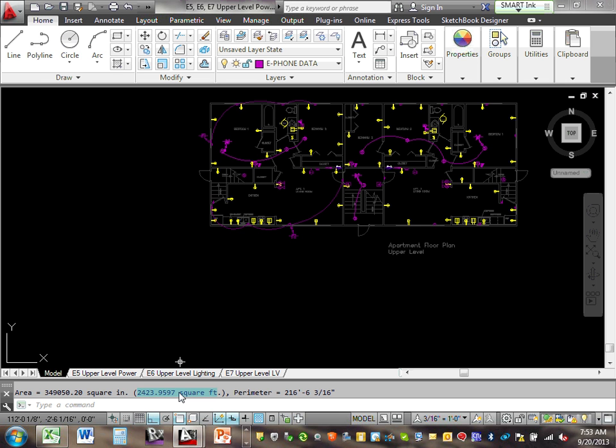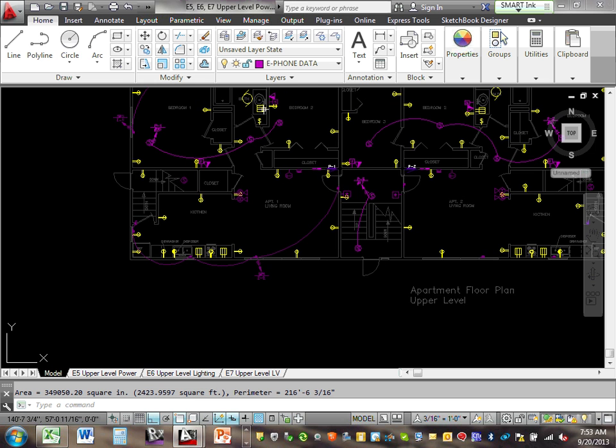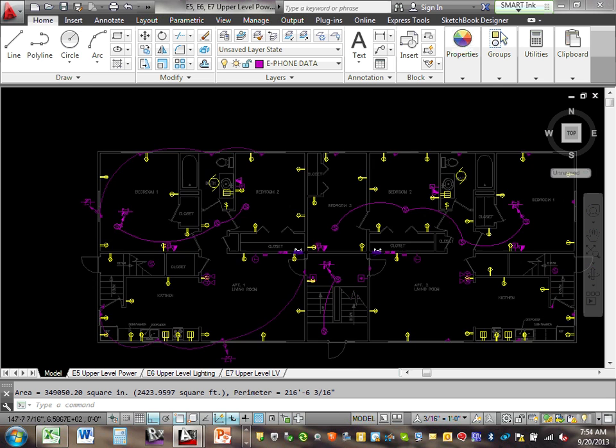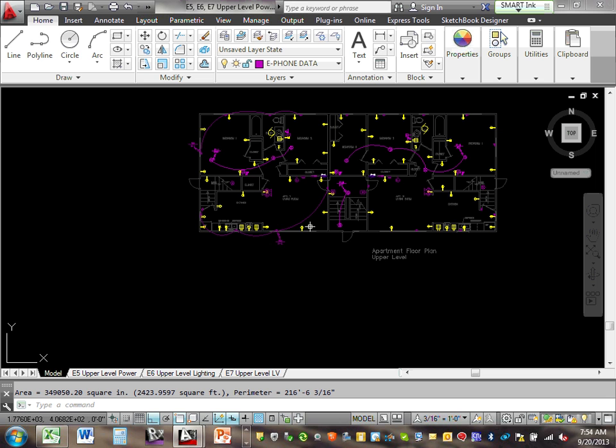The NEC code book, guys, says you have to count the habitable area. So we're not going to split here, and we took all of it, 97% of this area is habitable area. So everybody knows where I came up with 2424 multiplied by 2, that will give you 4848.